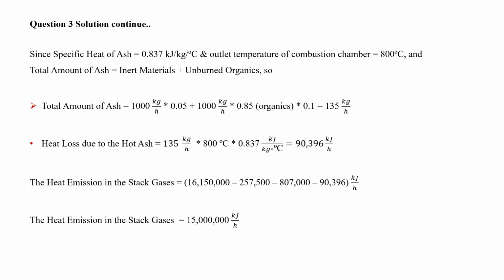But up to now, we did not include air in our heat calculations because in the question, again, it is assumed that the under and over fire air contributes negligible heat. But in our stack temperature calculation, we need to include this value since it is our transfer medium.